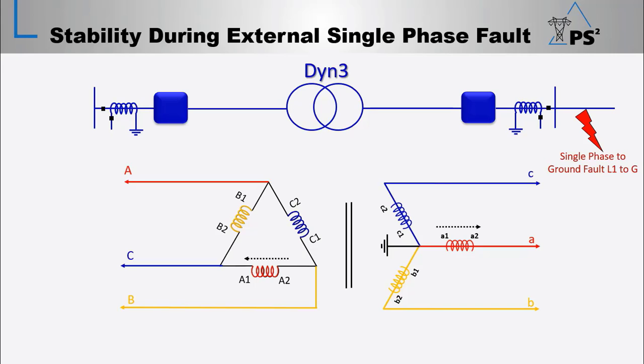No phase current on Y or B phases on the delta side, so the phase current of the R phase would flow to the line terminals in this direction. As we can see here, the line current in the star side would be detected by the CT of the red phase, while the line currents in the delta side would be detected by the CT of phases B and C. As the differential calculation is done phase-wise, in this case the relay would issue a trip. Sure, this will not be the relay action.